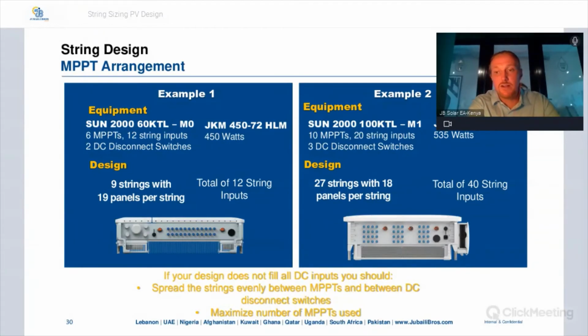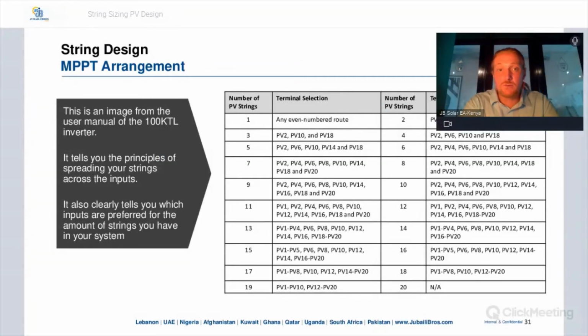On the left side, the 60 kilowatt inverter has 2 DC disconnect switches. They each control half of the MPPTs. And on the right side, the 100 KTL inverter has 3 DC disconnect switches. Each one controls the block of MPPTs that it is next to. So step one for optimizing is you should spread your strings evenly between the DC disconnect switches. The second part of the theory is you maximize the MPPTs, so you should not have any unused MPPTs. Part one is you spread your strings evenly between the switches, and part two is you maximize the MPPTs. But you can find this in the user manual. It will tell you exactly.